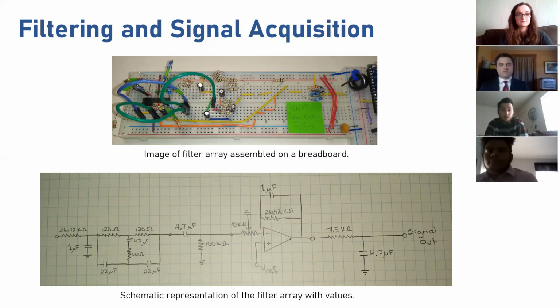Second, there is a notch filter designed to attenuate 60 Hz electrical noise as seen in residential housing, and this filter would have to be adapted based on location of use, as military electrical runs on 400 Hz, and therefore military craft would require a 400 Hz notch filter. Following that is our 0.8 Hz high-pass filter, corresponding to a heart rate of 48 beats per minute on the low side.